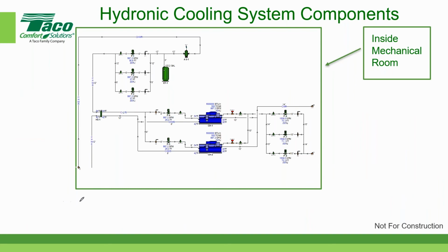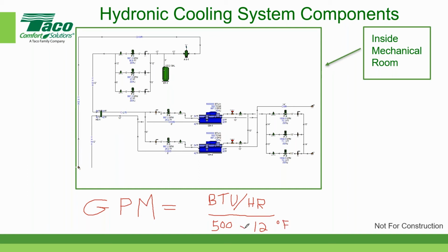So when we talk about GPM, there's GPM right there. We have a formula. In hydronics, the GPM is equal to the BTUs per hour, BTUs per hour, divided by a constant of 500 and divided by the delta T, which in our case we said was 12 degrees Fahrenheit. Now, how many BTUs are there in a ton?